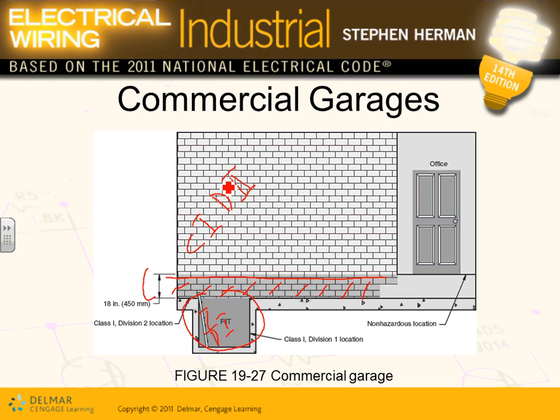Who cares? If you put a wiring method there, it's going to be explosion proof boxes. So in a commercial garage, when you design a system, you have to make sure that your system is above this area. And they have requirements for the light that you put here. Your light has to be enclosed so it doesn't drop and ignite the surroundings if it accidentally falls. But in the garage, 18 inches above the floor in all directions inside the garage where they fix the car is called a class 1 div 2 location. So you're going to see most people put the receptacles higher than 18 inches. Otherwise, you have to have explosion-proof receptacles. Okay, so that's your garage, and there has to be separation between the office and where they fix the cars.